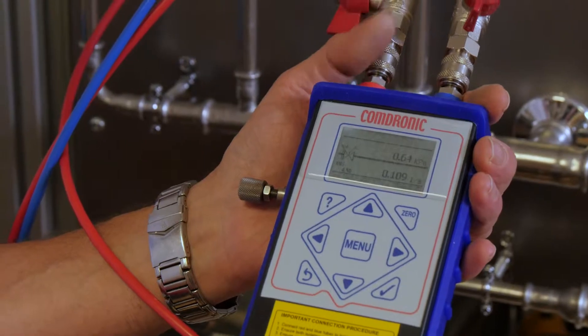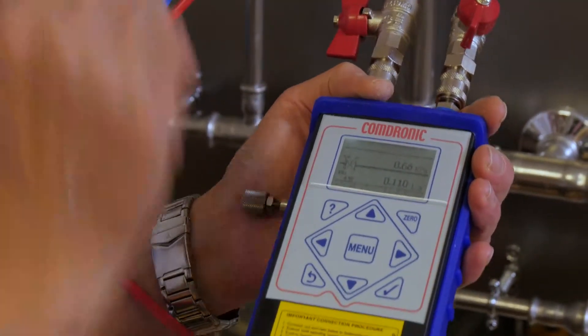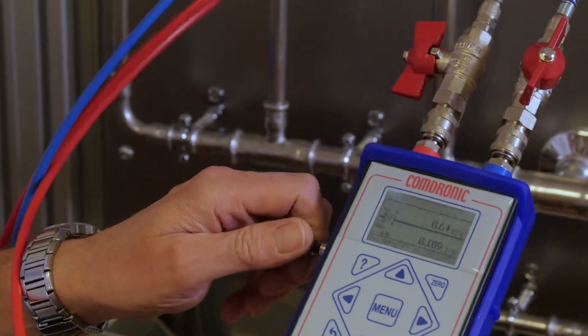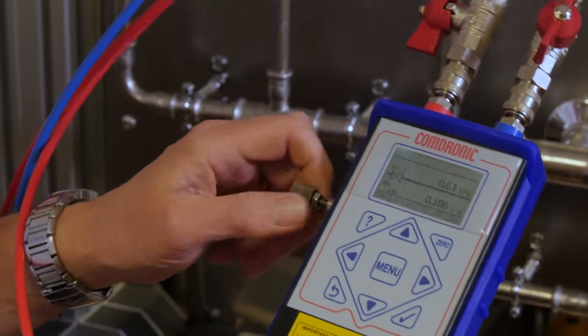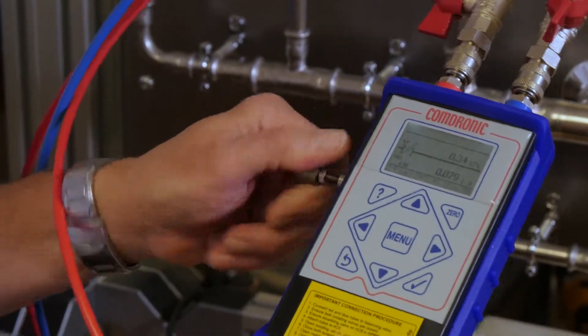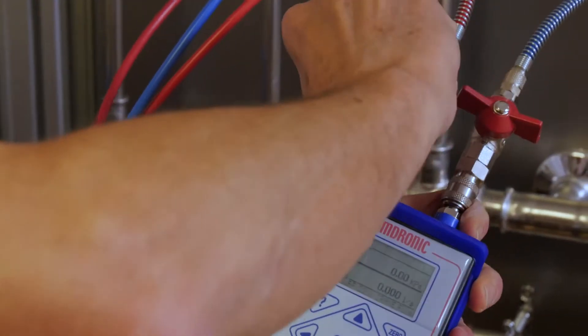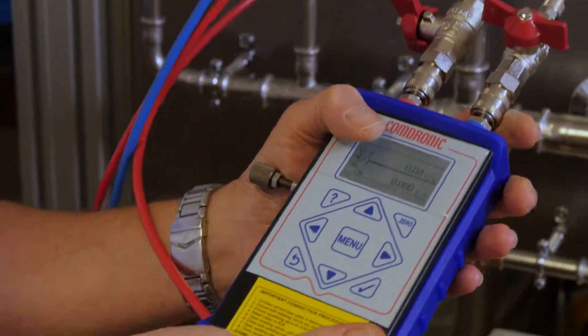Once we're at the flow rate that's required we can then lock the valve into position. And we've finished with this particular valve. So we can now open the equalizing valve. Close the valves on the hoses. And we can disconnect from the system.